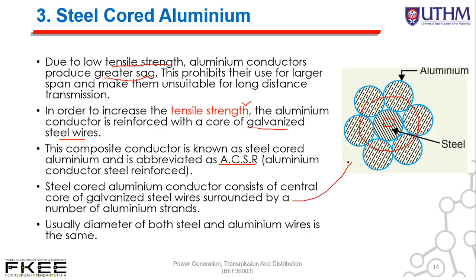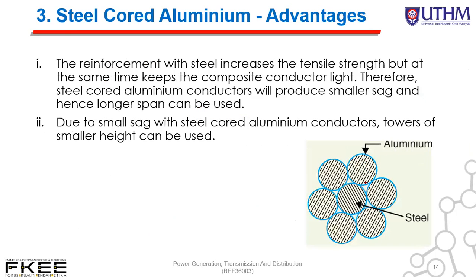We have seen this figure before. Usually, the diameter of both steel and aluminum wire is the same. And the advantages of steel core aluminum: first, the reinforcement with steel increases the tensile strength, which means the strength is increased but at the same time keeps the composite conductor light. Therefore, steel core aluminum conductor will produce smaller sag and hence longer spans can be used. Due to small sag, towers of smaller height can also be used.